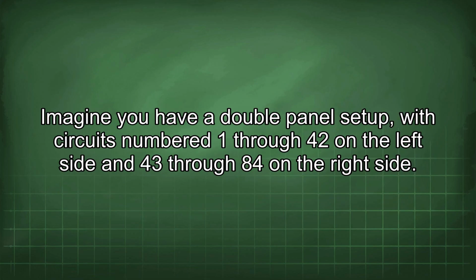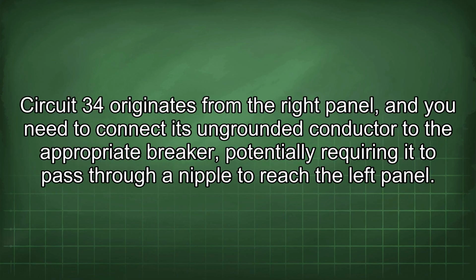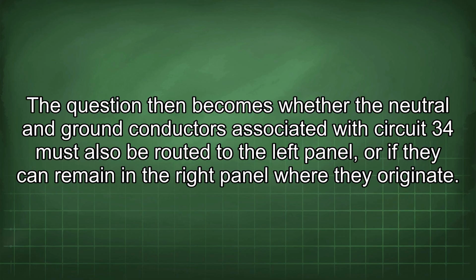Imagine you have a double panel setup with circuits numbered 1 through 42 on the left side and 43 through 84 on the right side. Circuit 34 originates from the right panel, and you need to connect its ungrounded conductor to the appropriate breaker, potentially requiring it to pass through a nipple to reach the left panel. The question then becomes whether the neutral and ground conductors associated with circuit 34 must also be routed to the left panel, or if they can remain in the right panel where they originate.